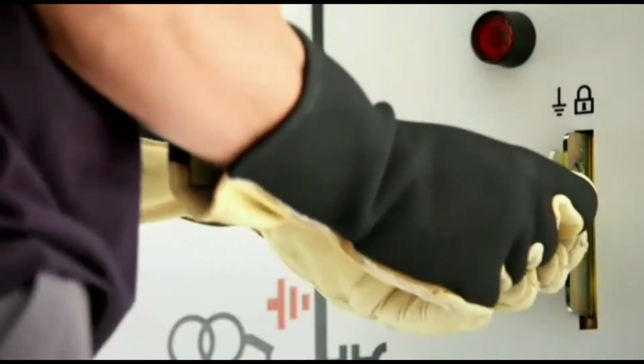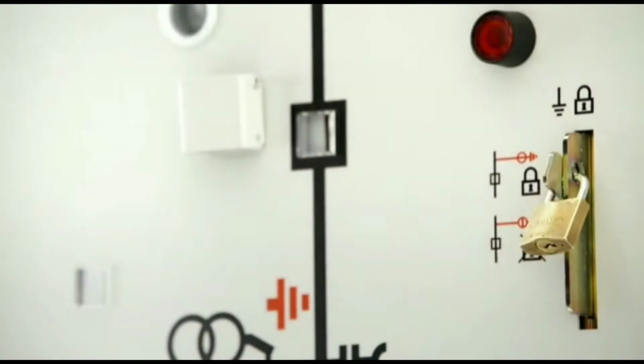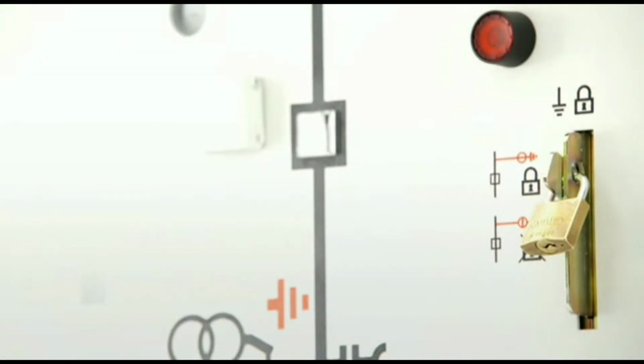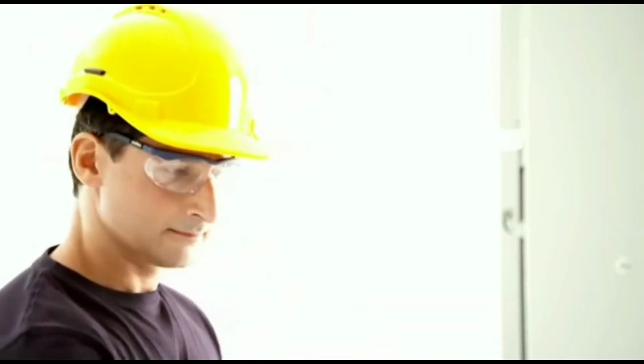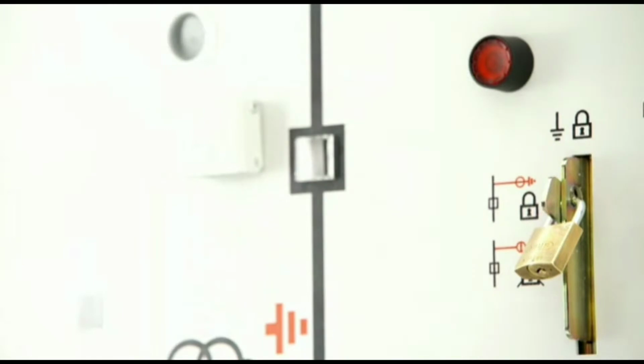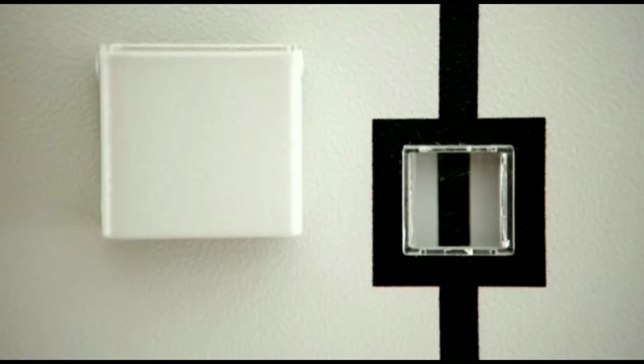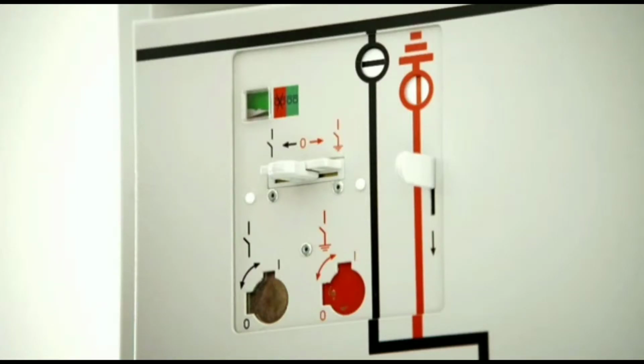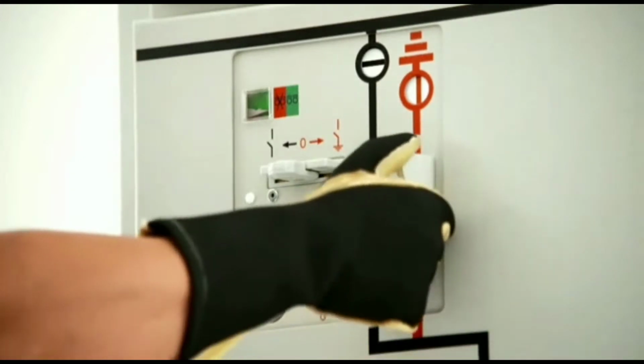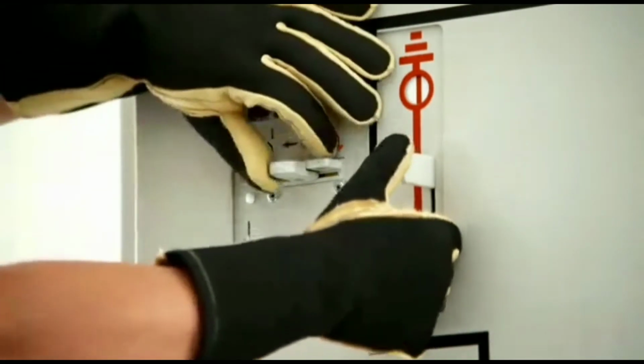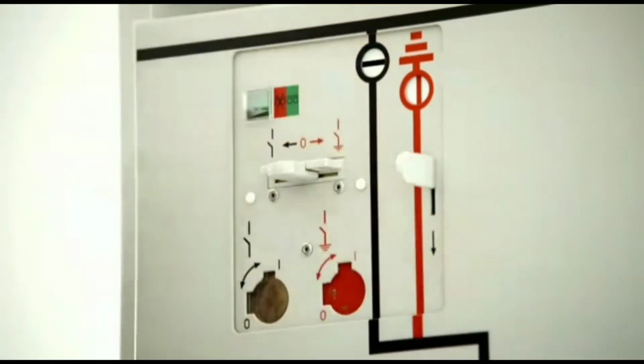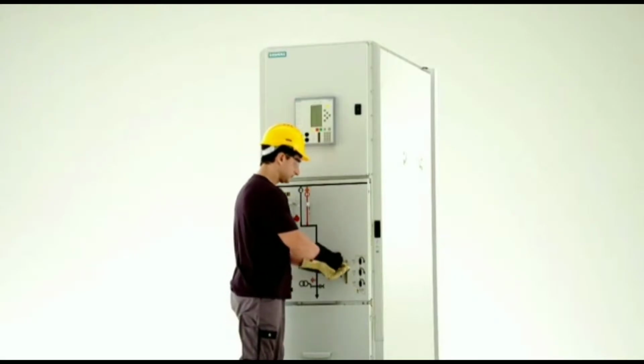A locking device interlocks the switchgear in the current switch position. De-earthing this feeder is now disabled, i.e. the circuit breaker cannot be switched to the open position. The mechanical interlocking between the circuit breaker and the three-position disconnector also makes it impossible to operate the three-position disconnector. This prevents maloperation and is a definite plus for personal safety.